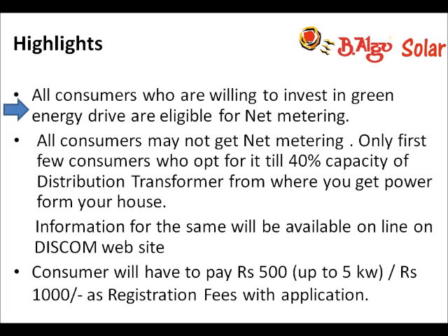All consumers of electricity in Maharashtra who wish to go green are eligible to avail this scheme. But all consumers cannot be allowed to go in for net metering. The limitation is the capacity of the distribution transformer of your DISCOM which feeds power to you. Solar injection to a maximum of 40% of the transformer capacity can only be connected. This sanction will be on a first come first serve basis for a given transformer and the information of available capacity will be made available on the website of the DISCOM. Consumers will have to pay Rs 500 as registration charges up to 5 kilowatt and Rs 1000 above that.